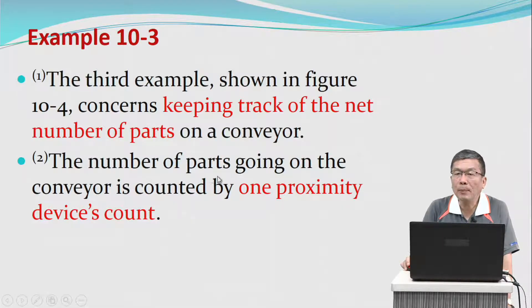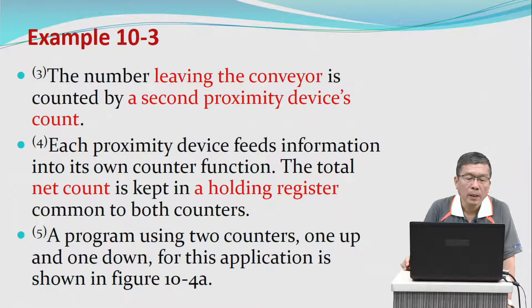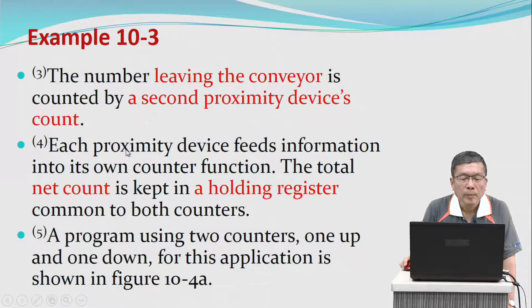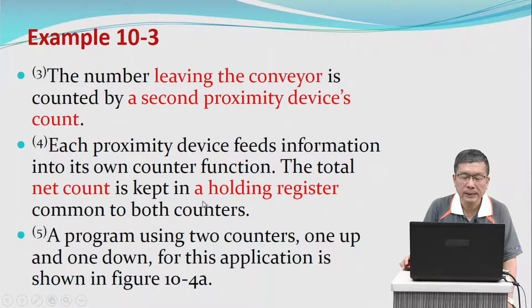The number of parts going on the conveyor is counted by one proximity device's counter. The number leaving the conveyor is counted by a second proximity device counter. Each proximity device feeds information into its own counter function. The total net count is kept in a holding register common to both counters.